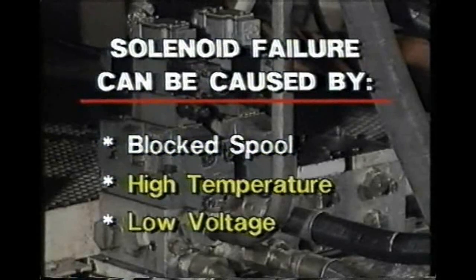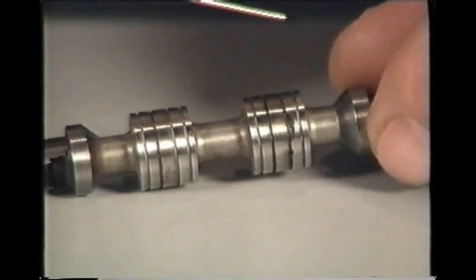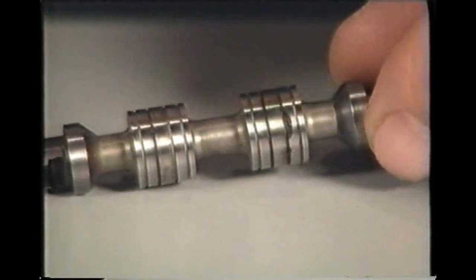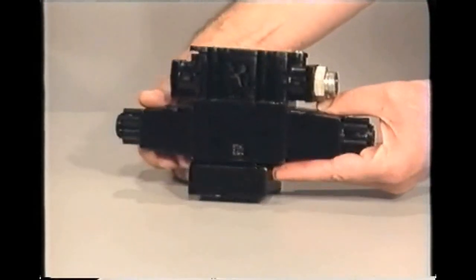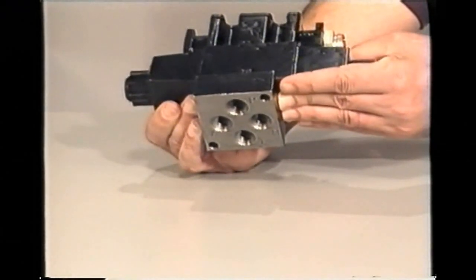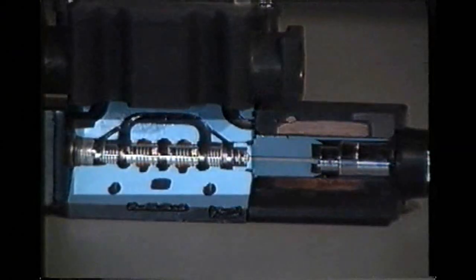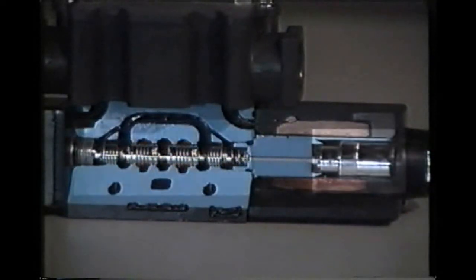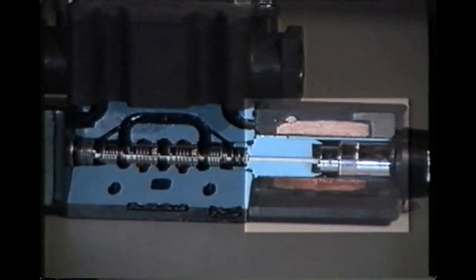Blockage usually occurs when the spool cannot move freely. Often this is due to some kind of contamination, silt in the valve or varnish on the spool for example. Sometimes spools will stick because the valves are improperly mounted on slightly warped or damaged subplates. If the spool does not move freely, the plunger in the solenoid will be unable to seat properly. The high inrush current will not drop to the lower holding level and the solenoid will eventually burn out.